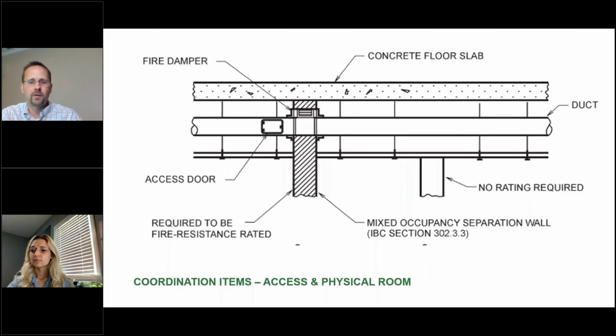And there are a number of different ways in which you can do that. Nowadays most projects are doing full coordination drawings. That really helps because those issues can be found before they're actually in the field and things can be offset. It's also important to coordinate in your own drawings, making sure that there aren't big banks of piping or conduit shown on all your own construction drawings blocking access to these dampers.